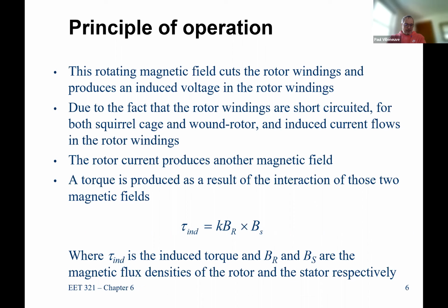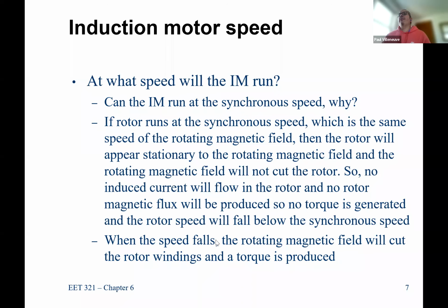So remember our data sheets where we looked at some nameplates and asked, what is the speed of operation? We looked at a bunch of data points and saw that the speed of operation was 1781 RPM, 1752 RPM, and so on. The synchronous speed on those machines is 1800 RPM, but the actual rotating speed is going to be less if it's a motor. If it's a generator, it would be higher. Okay, so that's how you can take an induction machine and make it operate as a motor or a generator.